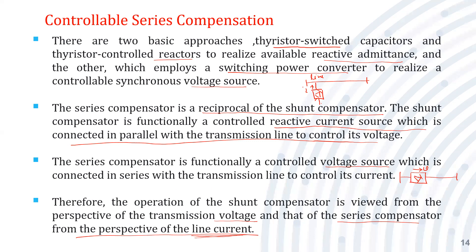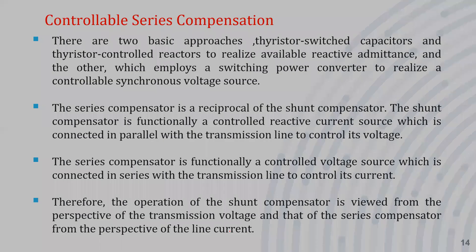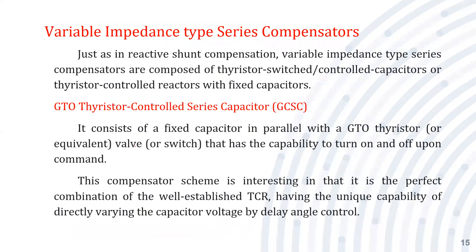The operation of the shunt compensator is viewed from the perspective of transmission voltage, while the series compensator is viewed from the perspective of line current. Controlling the line current allows the power handling capacity of the transmission line to be increased very effectively compared to shunt compensation. There are two types of series compensators: the switching converter type and the variable impedance type.